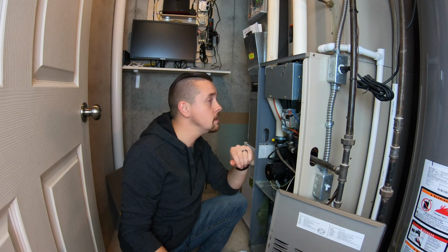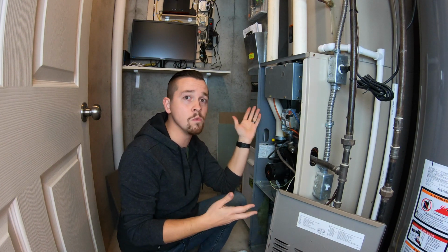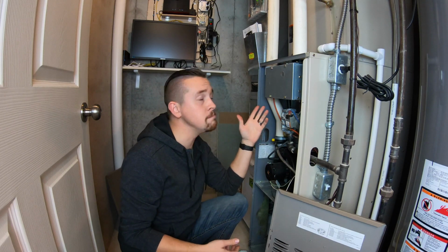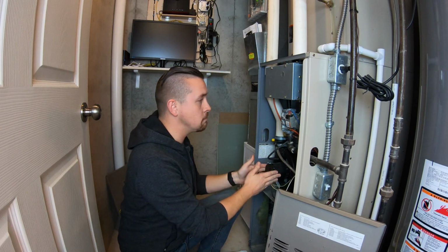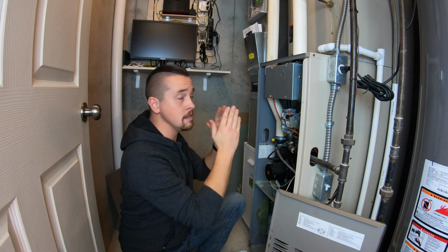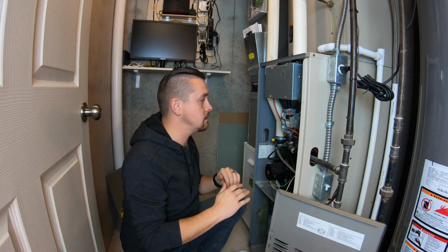I did a whole video on hot surface igniters as well. A hot surface igniter is what actually lights the burners inside of the burner compartment. If that's not working, it cannot light the burners, the gas won't light, and you'll have no heat. The symptom that you'll see is your inducer motor will be running, and then just nothing happens after that. You'll hear it probably turn off and turn back on a few times, and the burners will never light.